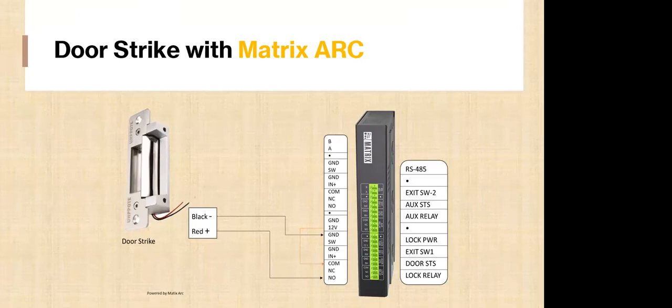Okay. And if the client wants to use 24 volt AC, can we power it using a separate power supply, and then bring that connection into the matrix? If it is AC, then we need to use a contactor because the relays which we are using over here are Form C dry contact relays.